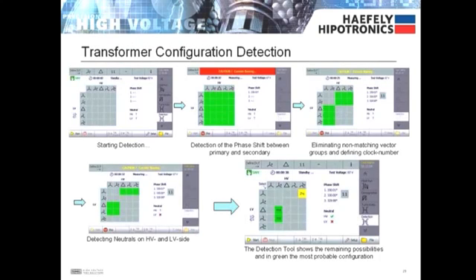At the start of the configuration detection, all configurations are possible as shown in green. Next, the 2293 detects the phase shift and eliminates non-matching vector groups. Next, the 2293 detects whether neutrals are present on the high voltage or low voltage side. Next, the 2293 will display the most probable remaining possibilities.